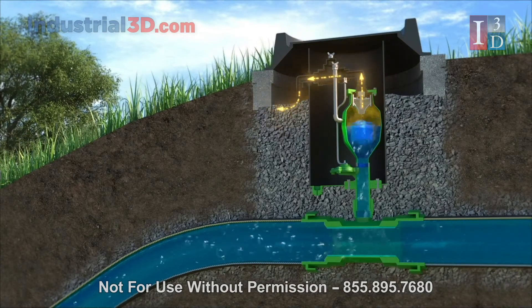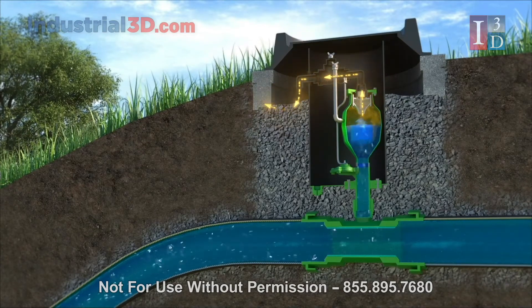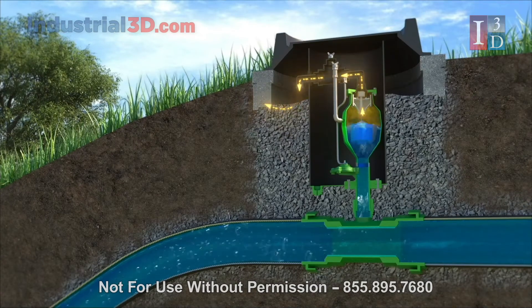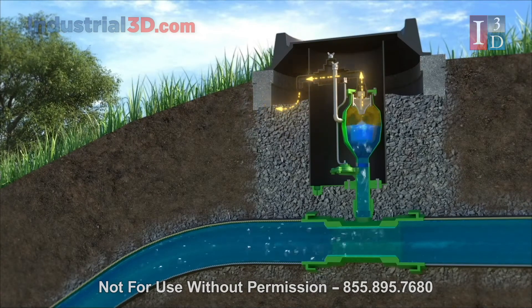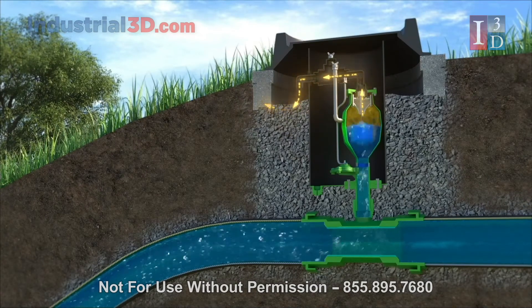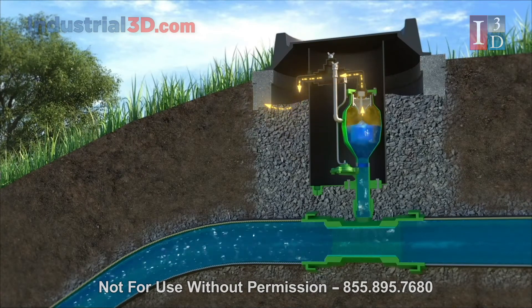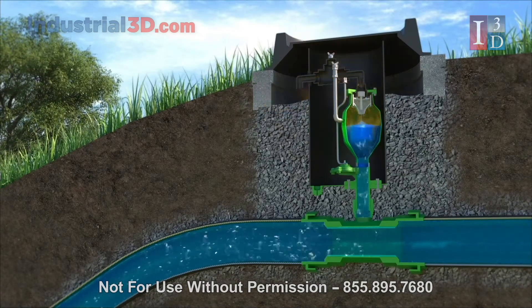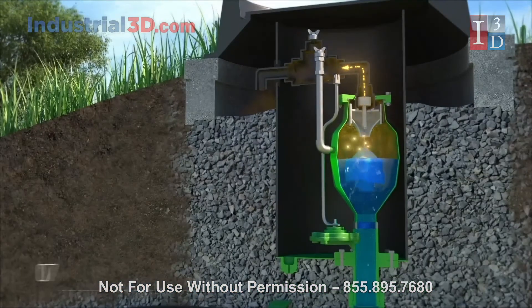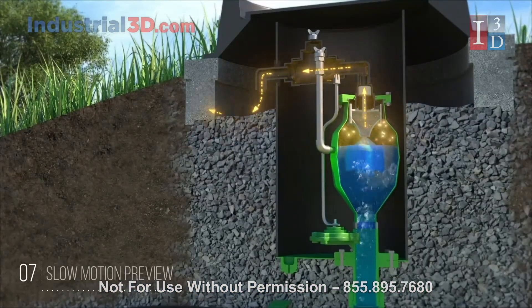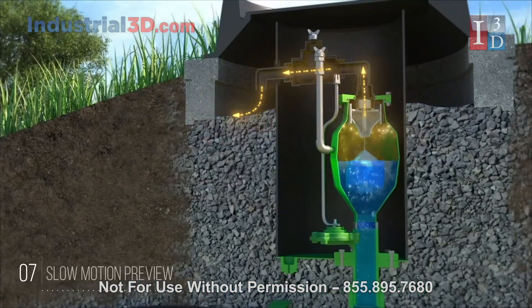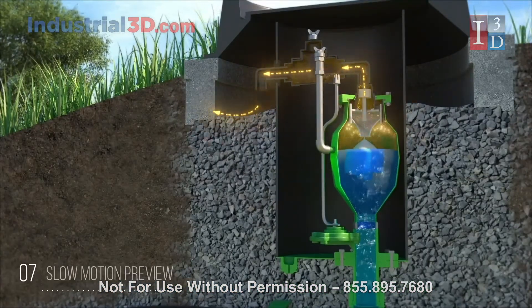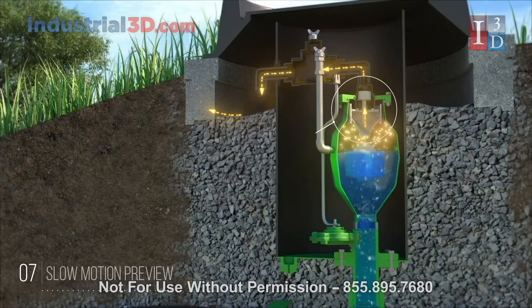As the media lifts the float, the diaphragm begins to partially close over the orifice, allowing gas and air to still escape. The debris shield protects the internal functioning unit from floating pollutants and non-organic particles.